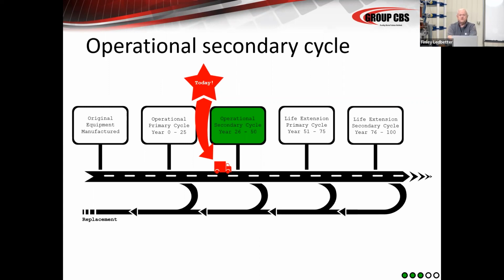After the first 25 years, we're going to go to the operational secondary cycle. So now your equipment has lived a good full 25-year life cycle. It's been shut down, cleaned, lubed, tested electrically and mechanically at least 4 or 5 times. You've found some deficiencies. You've found some issues. You've uncovered everything that was not caught in manufacturing or in acceptance testing, because you'll catch some things. There's some things you won't catch in acceptance testing that you'll catch in these 5-year checks. And there again, I'm not telling you to use 5 years.